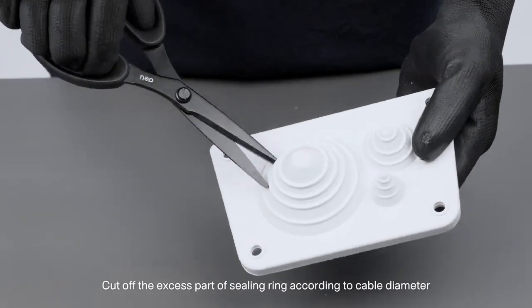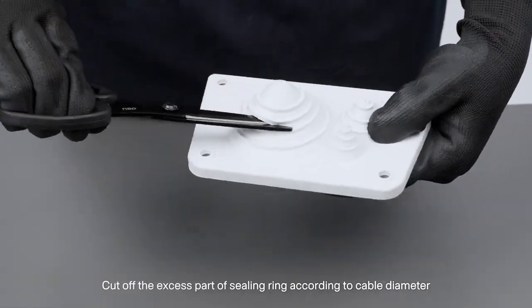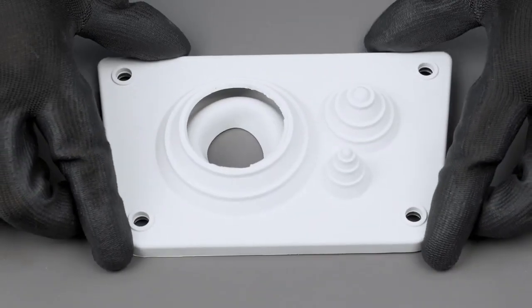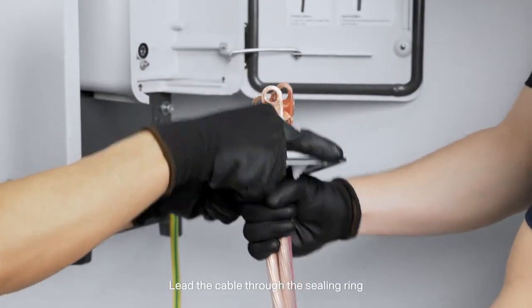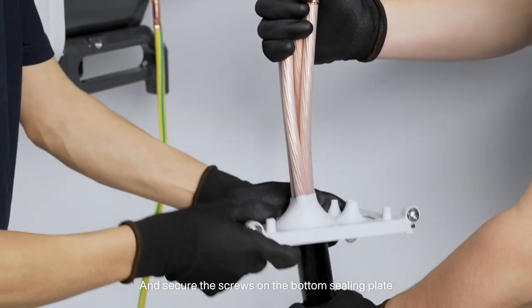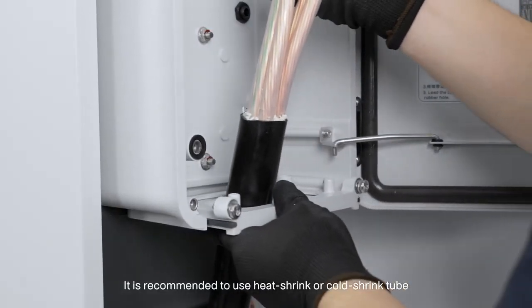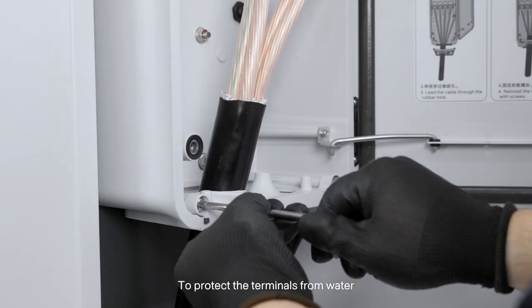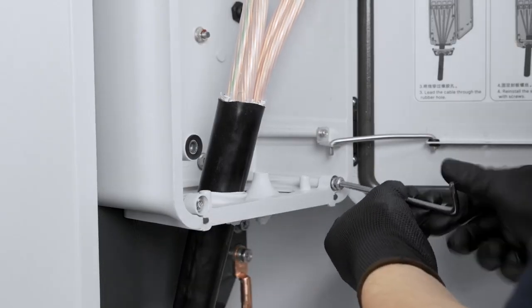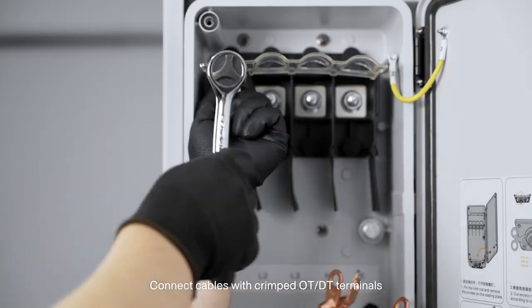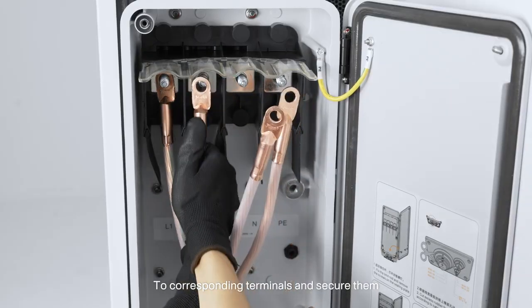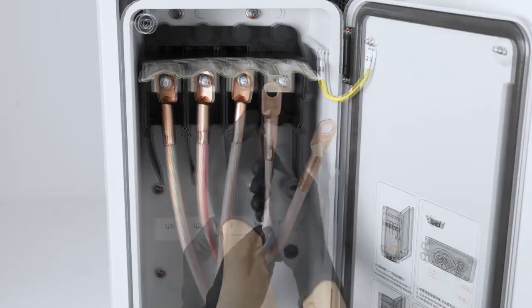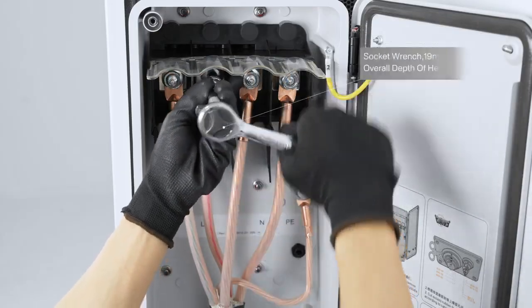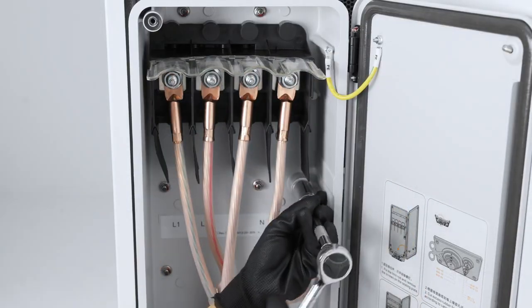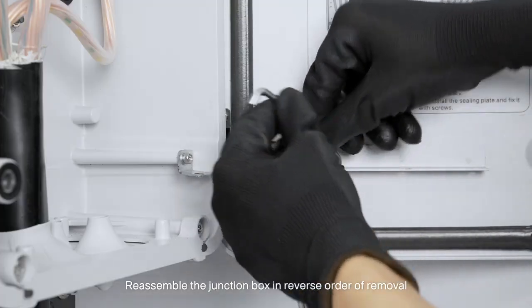Cut off the excess part of sealing ring according to cable diameter. Lead the cable through the sealing ring and secure the screws on the bottom sealing plate. It is recommended to use heat shrink or cold shrink tube to protect the terminals from water. Connect cables with crimped OT or DT terminals to corresponding terminals and secure them. Reassemble the junction box in reverse order of removal.